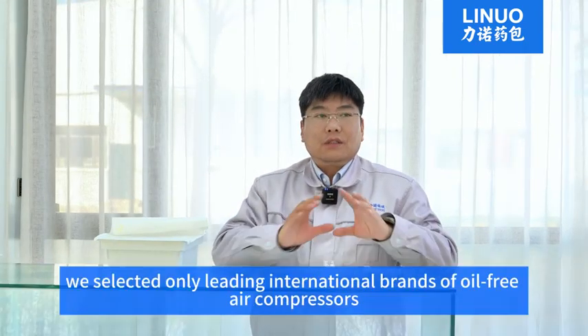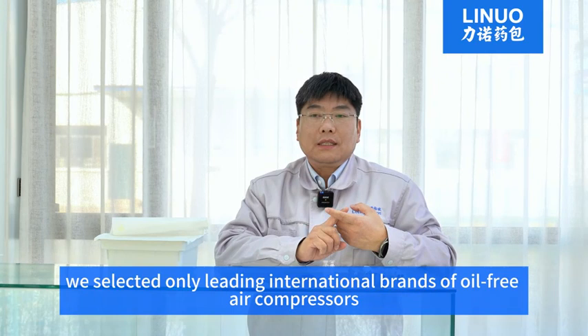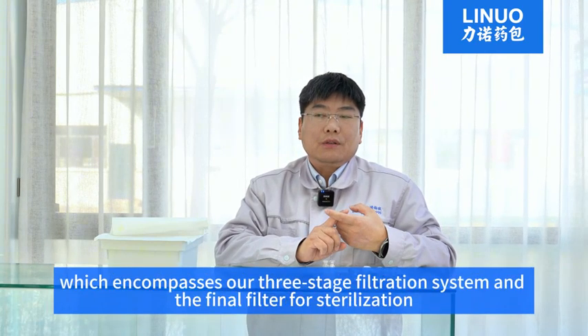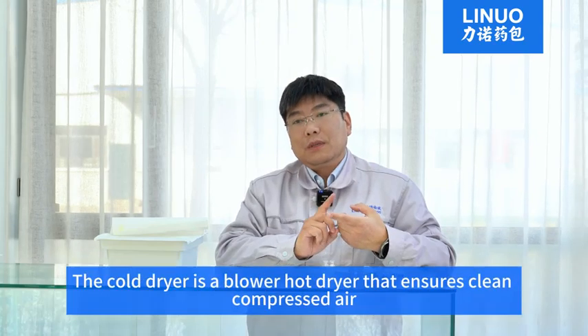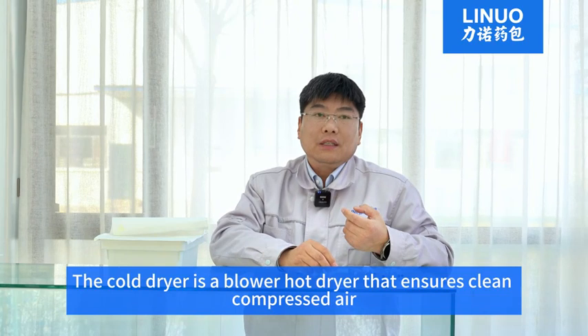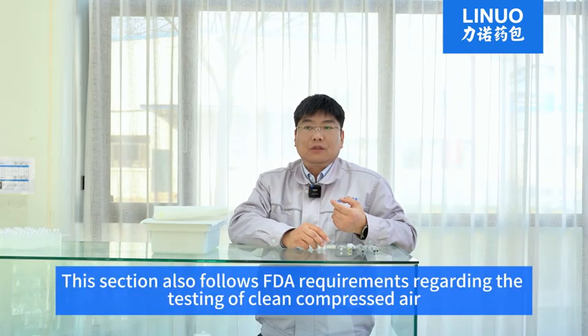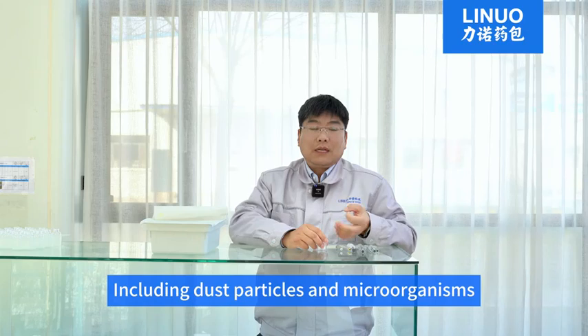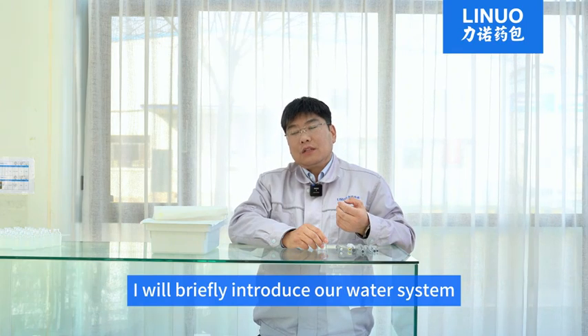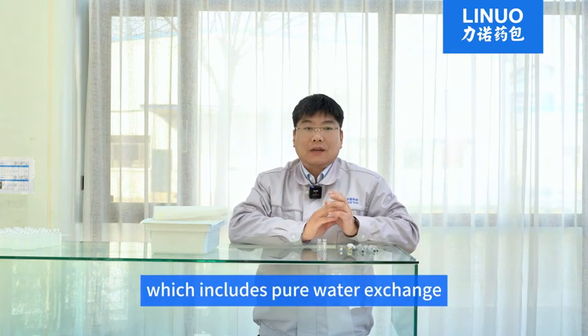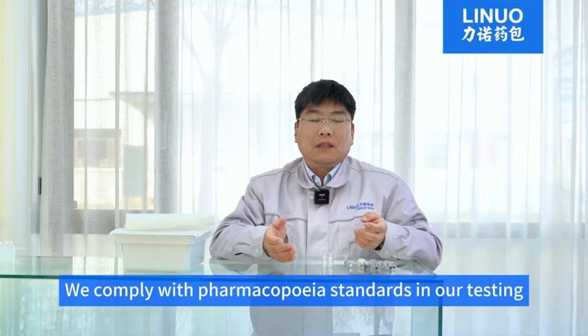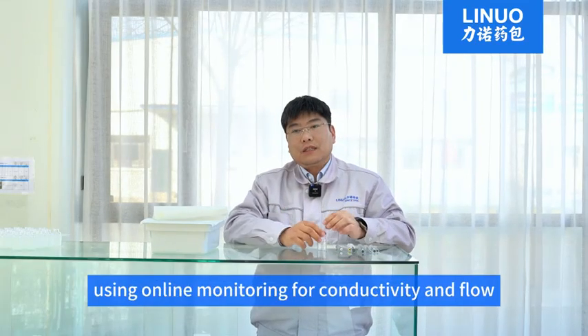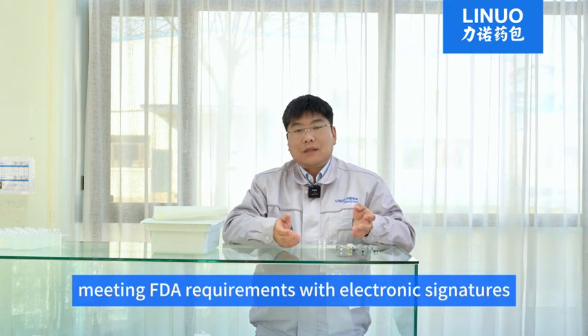During the whole process, we selected only leading international brands of oil-free air compressors, which encompasses our 3-stage filtration system and the final filter for sterilization. The cold dryer is a blower-hot dryer that ensures clean compressed air. This section also follows FDA requirements regarding the testing of clean compressed air. Oil and water levels, including dust particles and microorganisms. Now, I will briefly introduce our water system, designed according to FDA standards, which includes pure water exchange, injection water, and a distribution system. We comply with pharmaceutical standards in our testing, using online monitoring for conductivity and flow, meeting FDA requirements with electronic signatures.